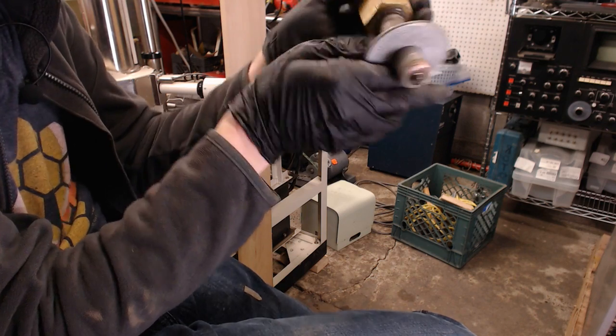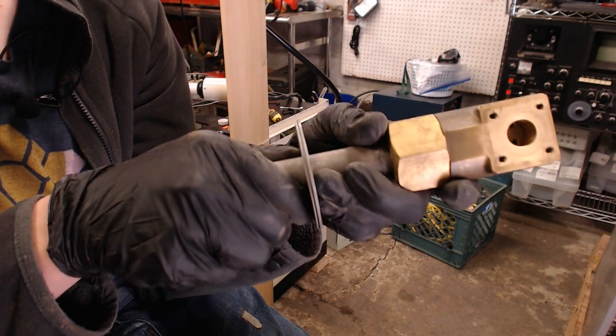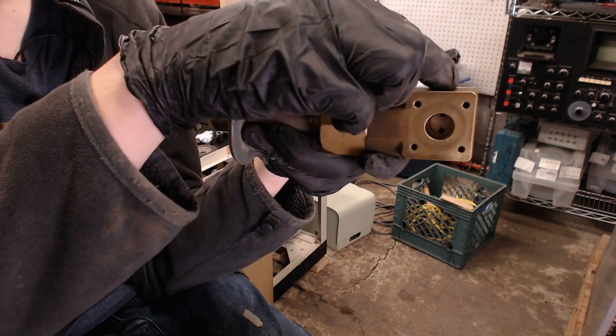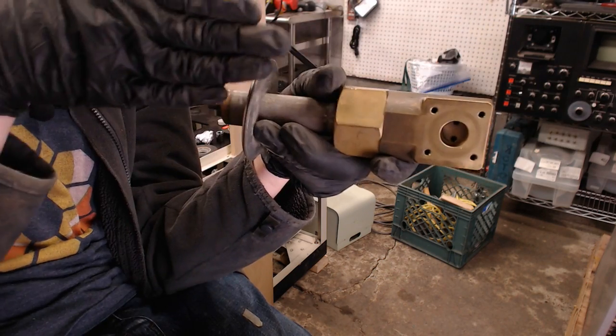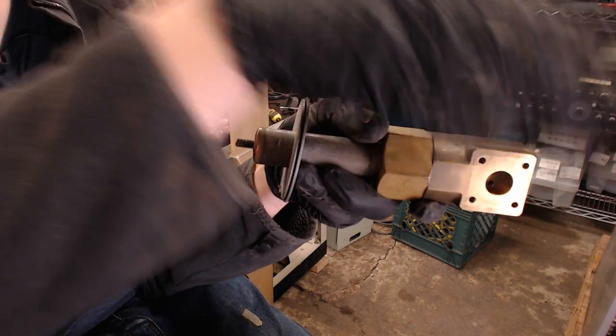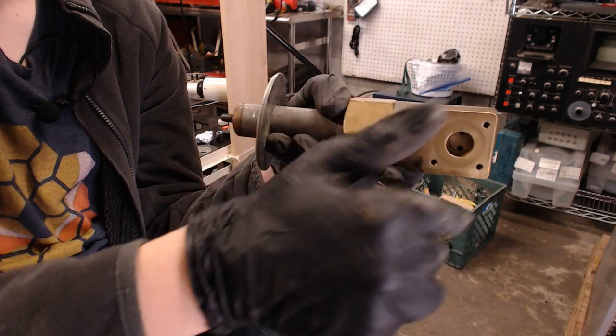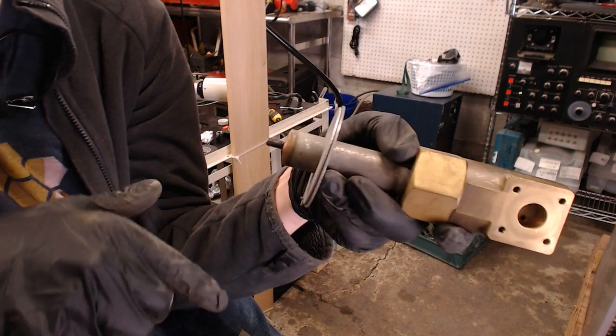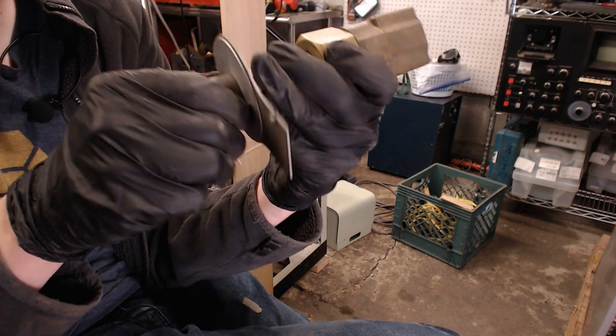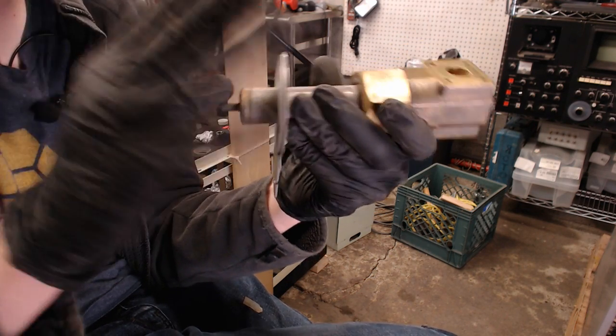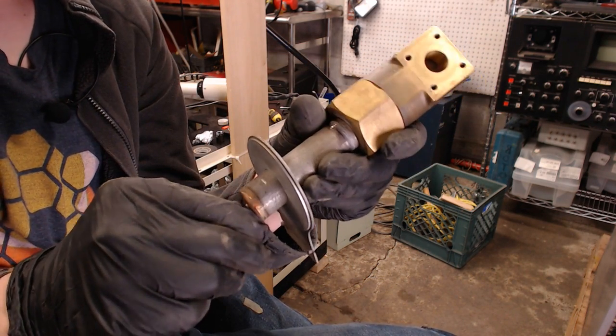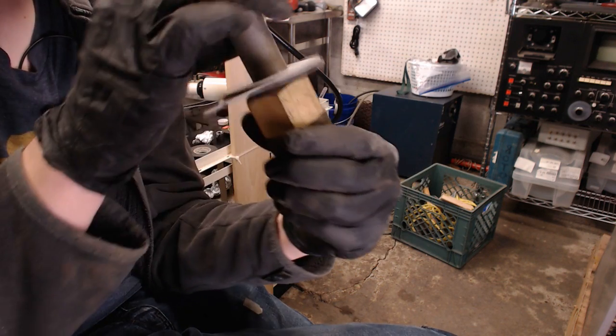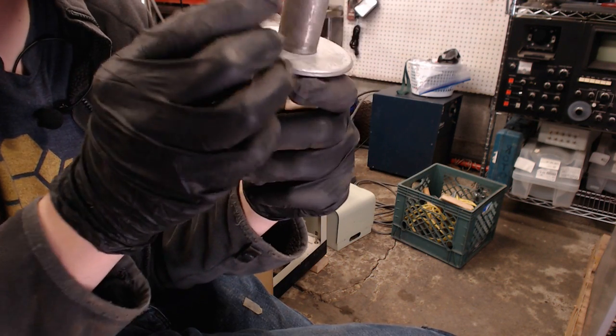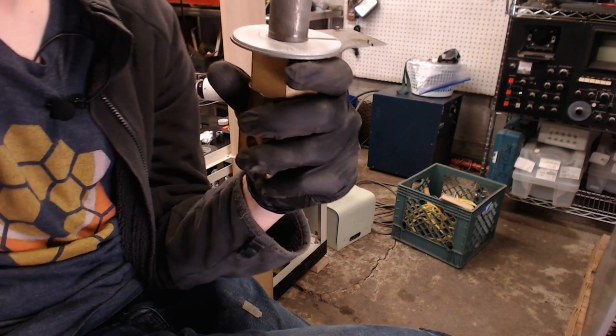In this copper piece down here, there's just a plunger that goes up and down. And if it's up, it's open. If it's down, it's closed. And then there's an O-ring seal on both sides of the plunger that it engages with. And then the electromagnet is what can pull it up. And then it's got a spring to push it back down. That way, if anything goes wrong with the power, the thing automatically shuts everything off. So I'll go ahead and put that back together now.